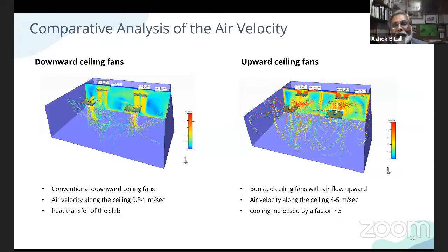Very, very interesting analysis was done in this particular building. A question was raised. We were going to use RCC slabs cooled by chilled water running through the slabs. Now someone says, what will happen if in the meeting room or in the conference room, suddenly 30 people arrive and it gets too warm? Your system of the chilled slab cannot react to that quickly, can it? Won't they feel uncomfortable?